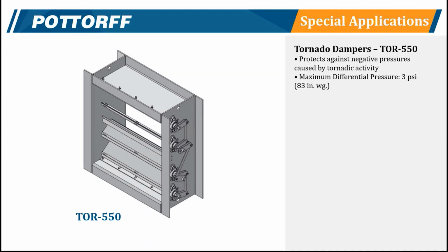Now, these are going to be at lighter pressures than our blast damper, so it's only going to be 3 psi, but that's still a pretty high pressure rating when you're talking about inches of water gauge. When you're looking at some of our other industrial control dampers that say only go up to 45 inches of water gauge, when you start going to PSI, that's just a higher factor of pressure and requires a much stronger damper. This should also allow us to be a bit more competitive, because using the same construction for the blast damper that is able to withstand 15 psi would be overkill for this 3 psi application.